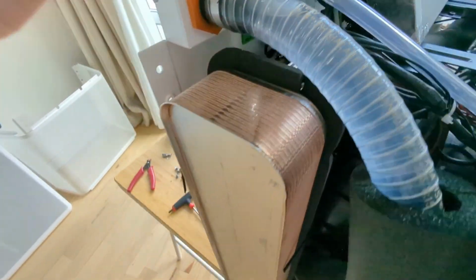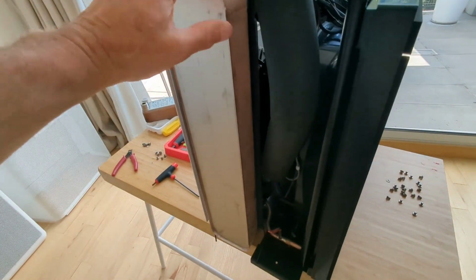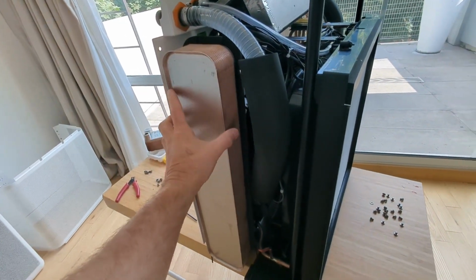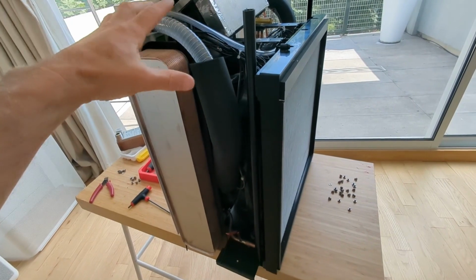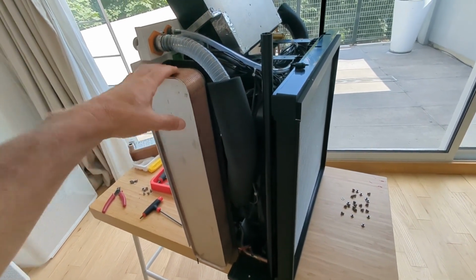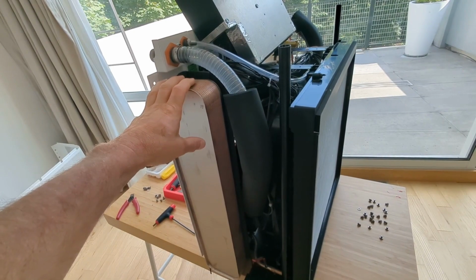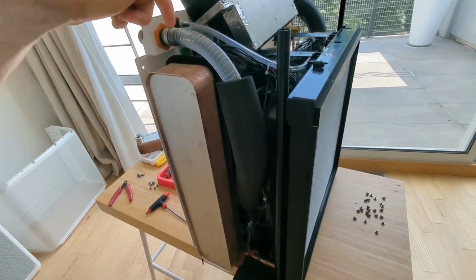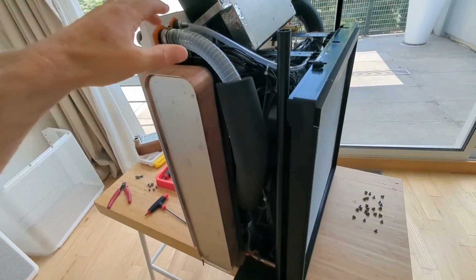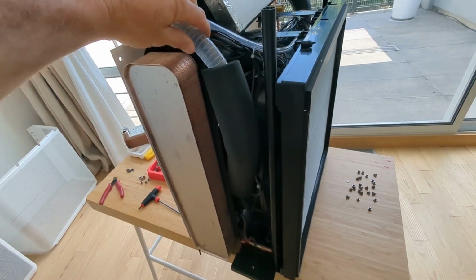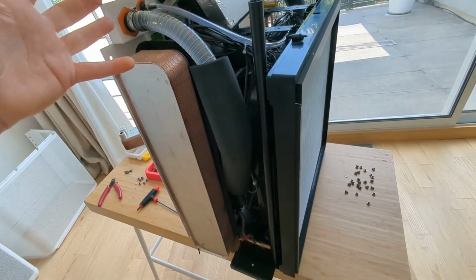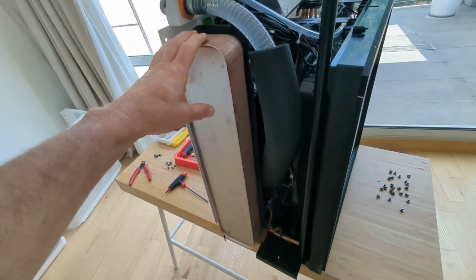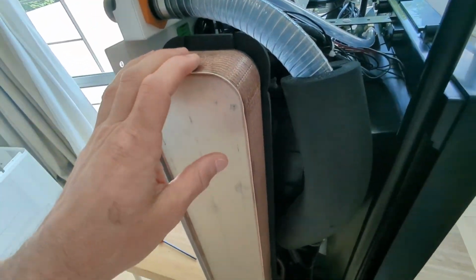Those are cool. And then this honking chunk of metal right here is the heat exchanger. This is what makes this unit into an air-to-water heat pump, as opposed to an air-to-air heat pump like a normal air conditioner window unit would be. Refrigerant goes in one side and out the other, and then the coolant goes in one side and out the other, and it exchanges the heat. So in air conditioning mode, you're gonna have liquid refrigerant going in here and hot water, and then vapor refrigerant and cold water coming out, and then that cold goes into your house, and you use that to cool the air inside your house. These are pretty amazing things.